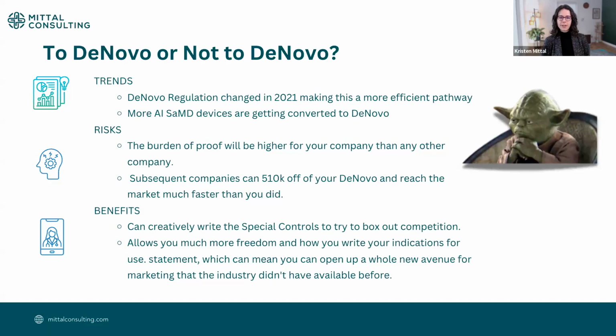So de novo regulations changed in 2021, making this a more efficient pathway. And we see more AI SaMD devices getting converted to de novo. This is what we've been seeing lately. The risk of this is that the burden of proof will be higher for your company than for any other company. So subsequent companies can 510(k) off of your de novo once you get to market, and they'll reach the market much faster than you did. So the review time for a de novo is longer on average than a 510(k).